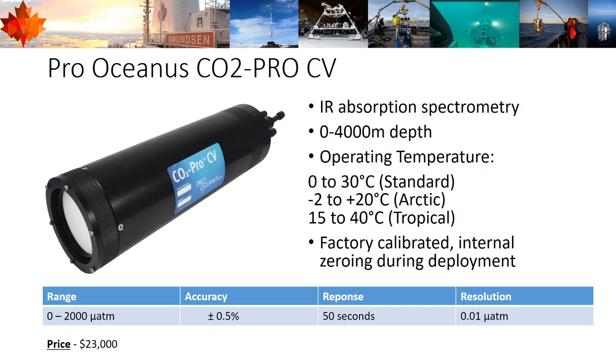So again, this is using that infrared absorption spectrometry method, and it's fairly comparable to what you saw previously with respect to response time and accuracy, but the big component here is the operating temperature that these things are capable of being deployed in is very tailored to the environment that they're going to see.